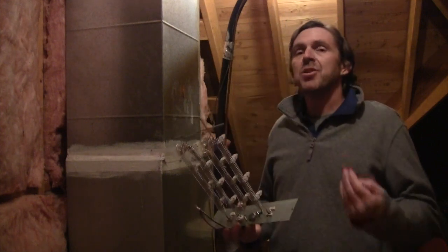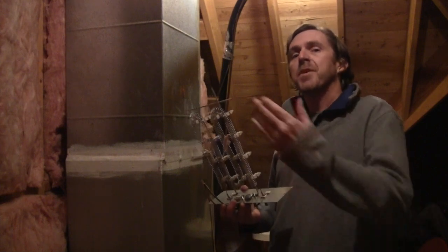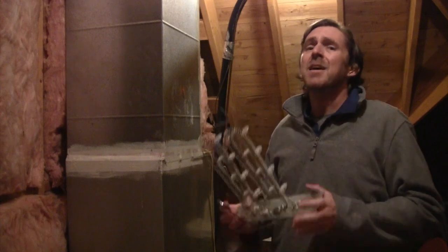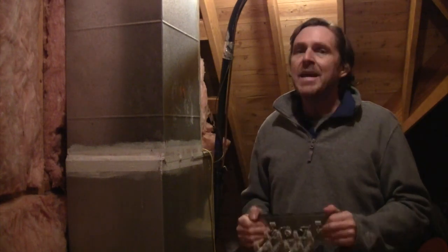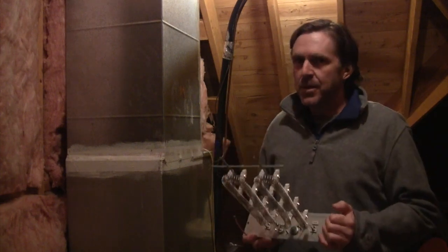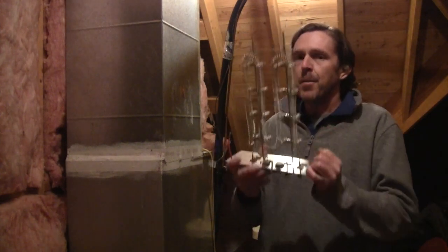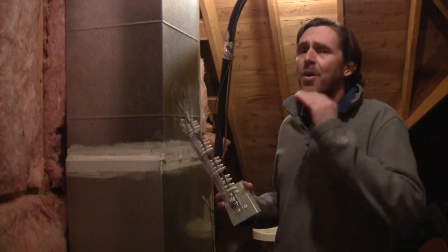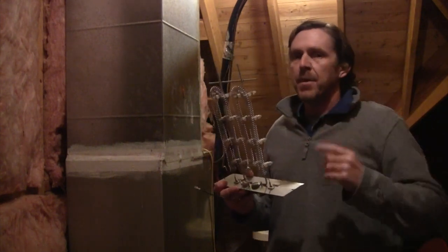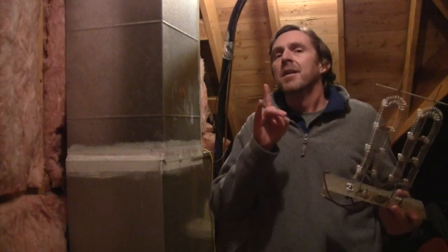So on colder days, you're going to use more energy because your heat pump is taking it about 3/4 of the way to the set point in the thermostat, but because it's so cold outside, it needs help from these elements. When you look on your thermostat and it says auxiliary heat, this is what this is talking about. But your outside units should still be running, and these are merely helping the heat pump to reach the set point.